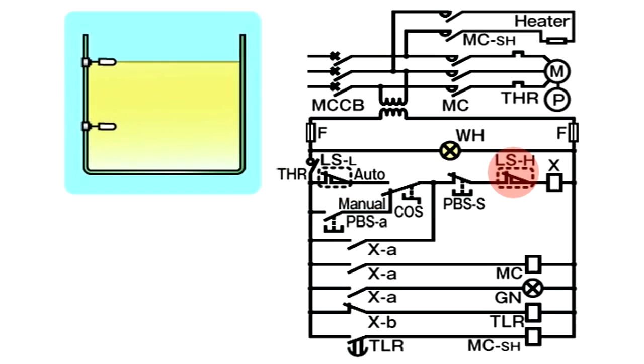The MC-coil is demagnetised as X-A turns off. As a result, MC-contactor turns off to interrupt the supply of power to the motor, bringing pump operation to a halt. As X-A turns off, the green operation lamp goes out. With X-B turned on, the timer TLR coil is excited. The TLR relay turns on after a set period of time elapses, and the MC-SH coil is excited. Then MC-SH contactor turns on, allowing current to flow to the space heater. This prevents the motor from accumulating condensation due to cooling.